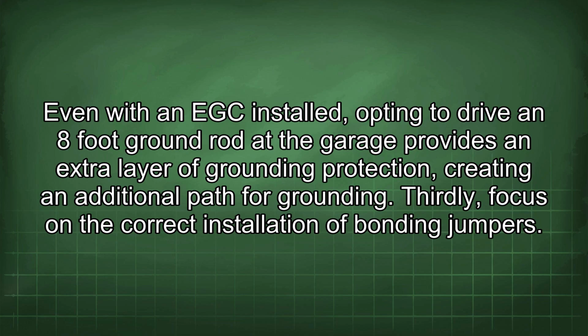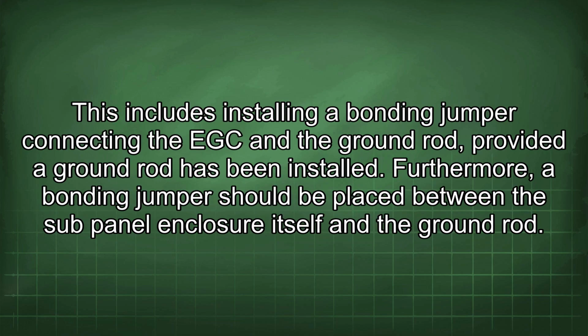Even with an EGC installed, opting to drive an 8-foot ground rod at the garage provides an extra layer of grounding protection, creating an additional path for grounding. Thirdly, focus on the correct installation of bonding jumpers. This includes installing a bonding jumper connecting the EGC and the ground rod, provided the ground rod has been installed. Furthermore, a bonding jumper should be placed between the sub-panel enclosure itself and the ground rod.